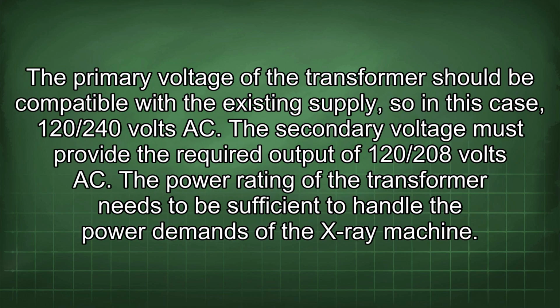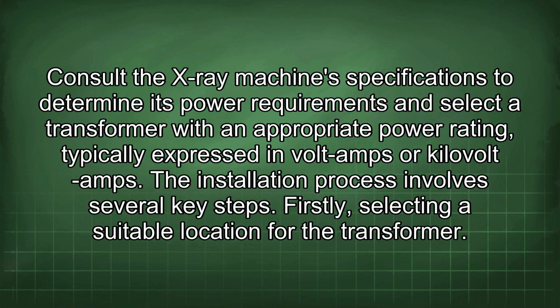The primary voltage of the transformer should be compatible with the existing supply, so in this case, 120/240 volts AC. The secondary voltage must provide the required output of 120/208 volts AC. The power rating of the transformer needs to be sufficient to handle the power demands of the X-ray machine. Consult the X-ray machine's specifications to determine its power requirements and select a transformer with an appropriate power rating, typically expressed in volt amps or kilovolt amps.